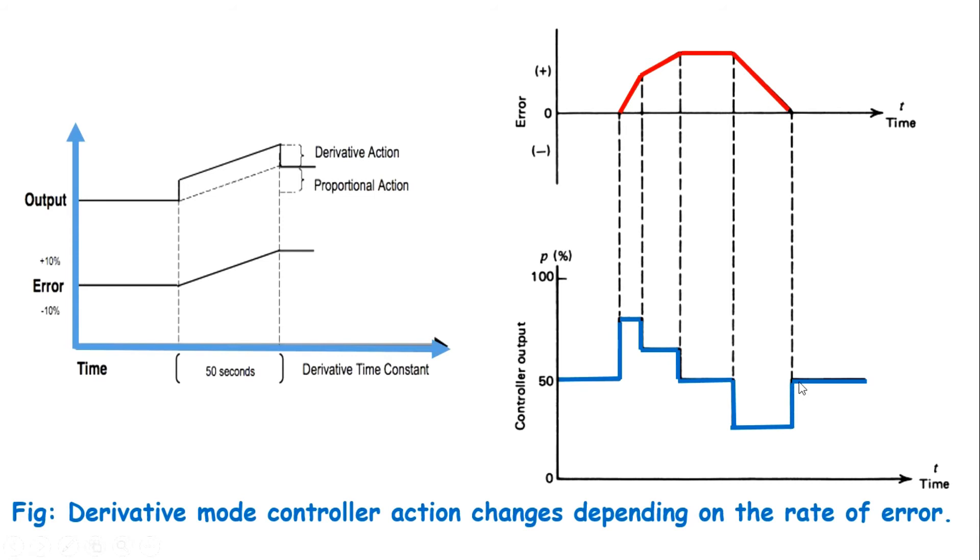The derivative mode must be used with great care and usually with a small gain because a rapid rate of change of error can cause very large sudden changes of controller output. Such an event can lead to instability.